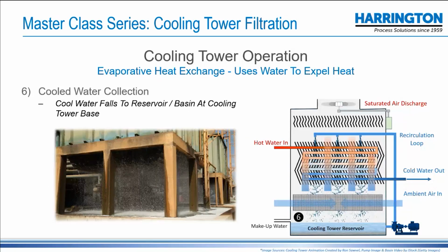Sometimes there's not even a screen. I mean, the basin, the reservoir itself can be open. My favorite story was a municipality that I was talking with, who came in one day and the workers came in and found a dead deer floating in the cooling tower. Now, I've seen pigeons and other dead animals there. That's an exception, not the rule. But I mean, it's open to the atmosphere. You can get anything that's in the atmosphere or running around the facility into that basin.